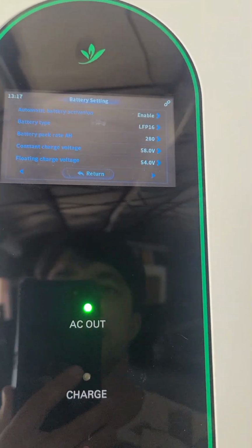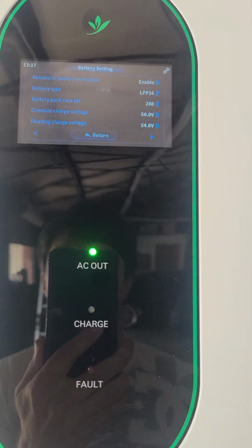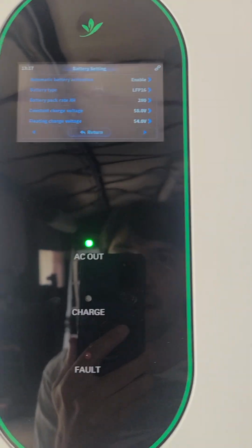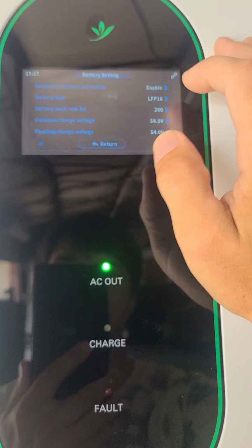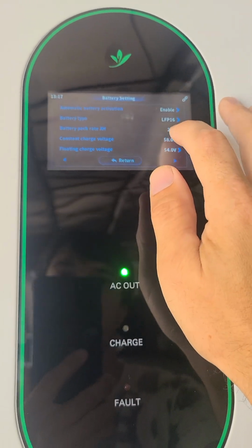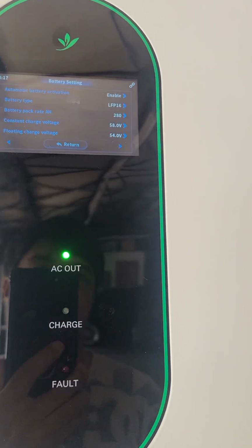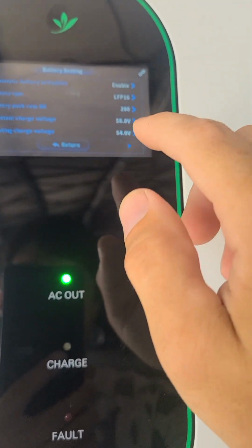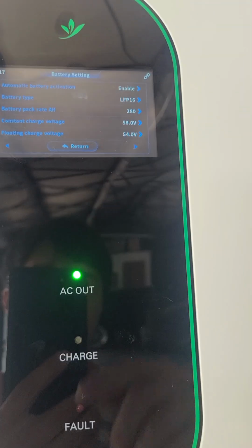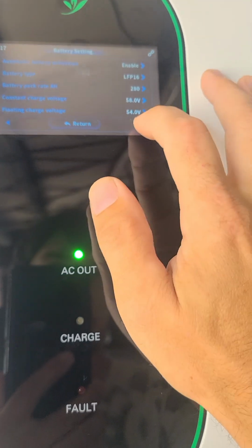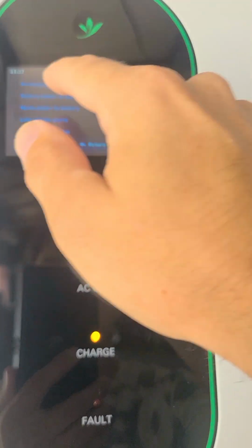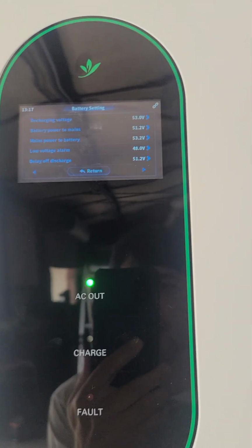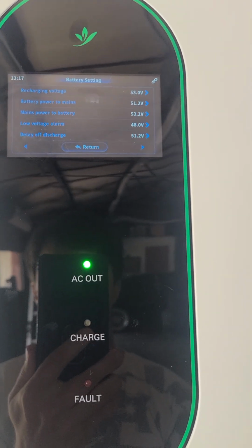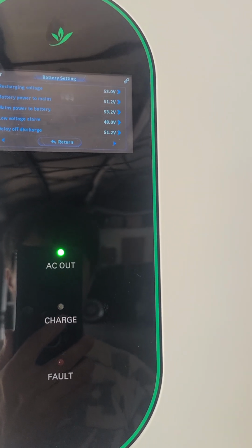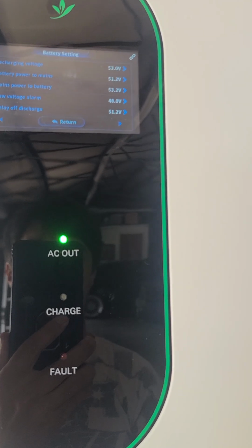So now we go into battery settings. Now, of course, I'm running LFP16. That's what a 51.2 volt setup is. The 280 amp hour, I think that's only for lead acid. I don't think that matters, but I said it anyway. Constant charge voltage, floating charge voltage, these are standard. 58 volt, 54 volt, those are standard settings for LFP16. Same with recharging voltage. That means that when we're below 53 volts, we want to charge the battery. We want to prioritize charging the battery.